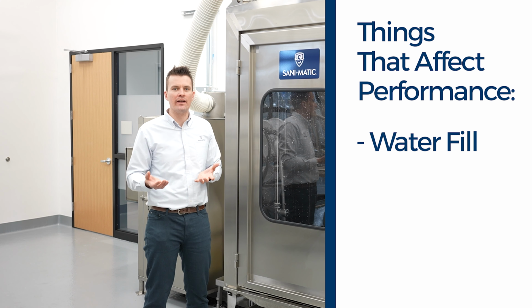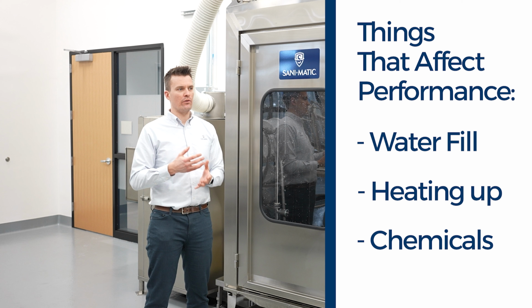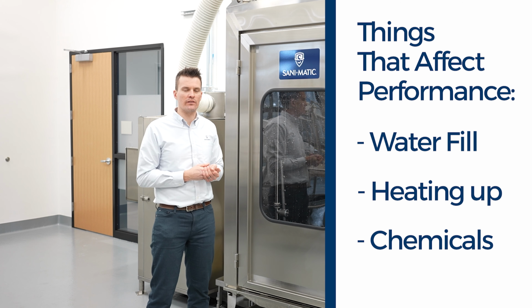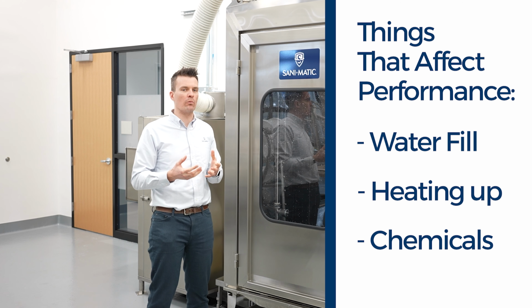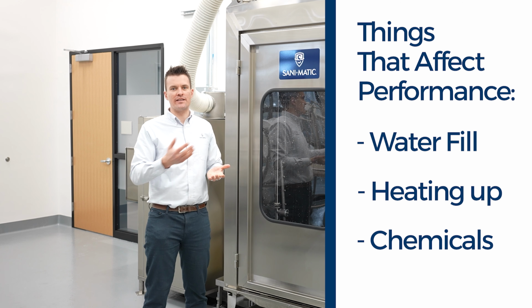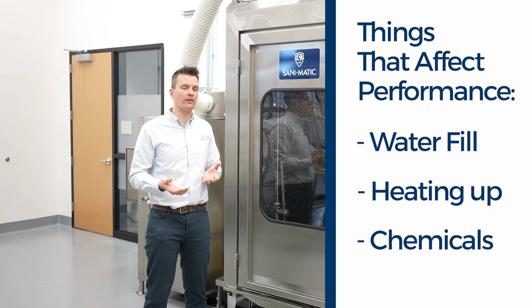Other things, heat up time. So as you're adding heat, whether it's electric or steam, if your utilities are fluctuating, that can lengthen the time to heat up. Chemical addition, so you're pumping in chemical for your chemical washes. If you have leaks or plugs in the chemical line or something's not quite working correctly there, you may extend the time that you're using to inject chemical.